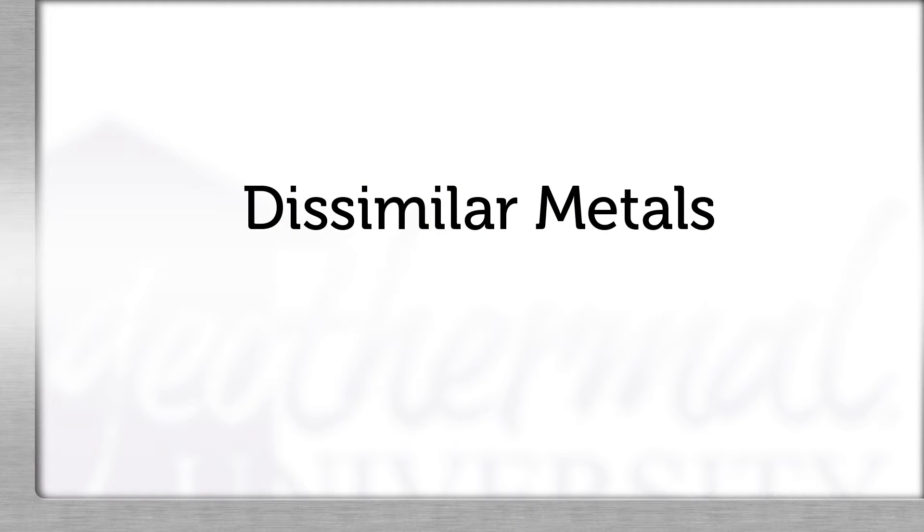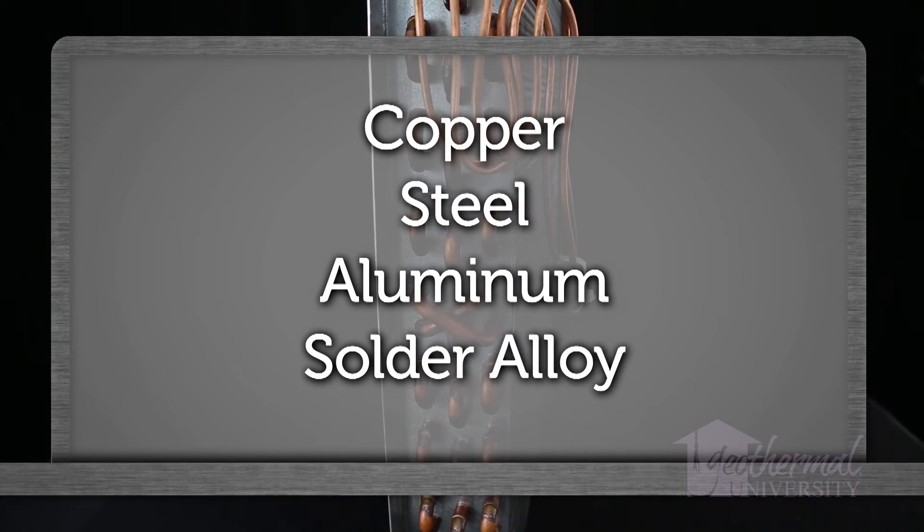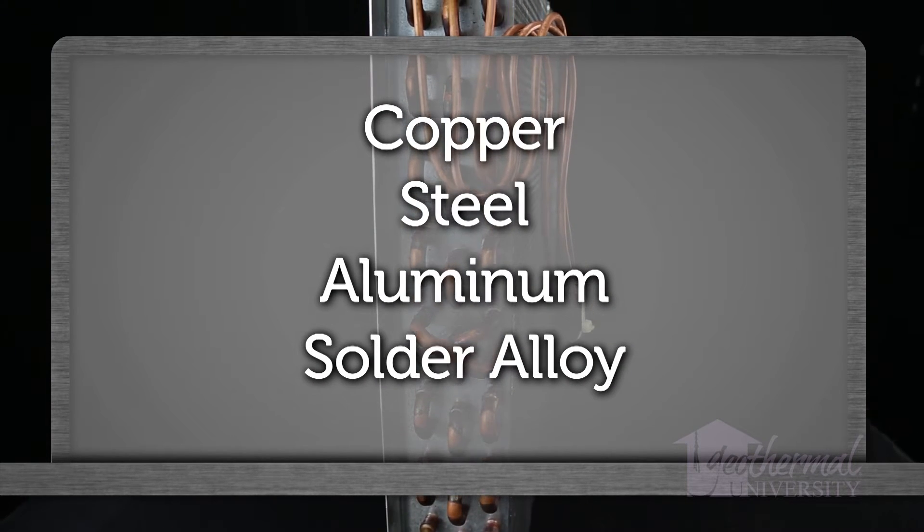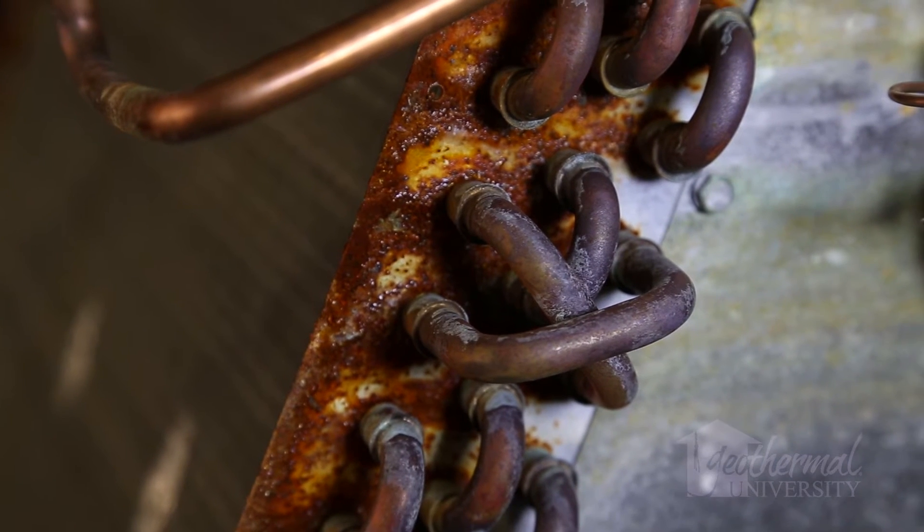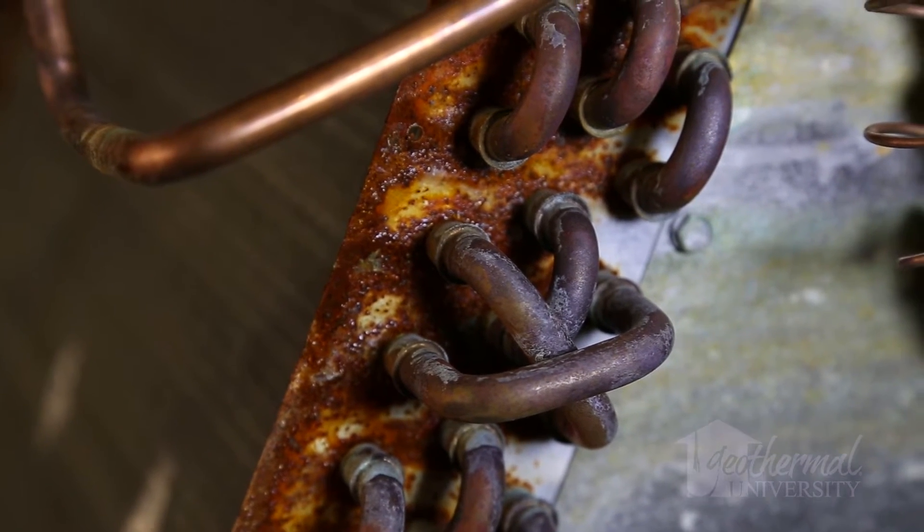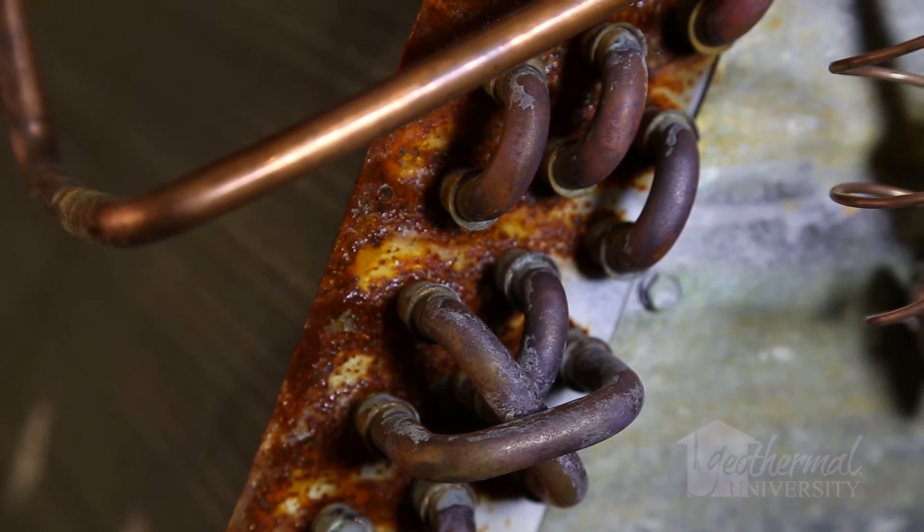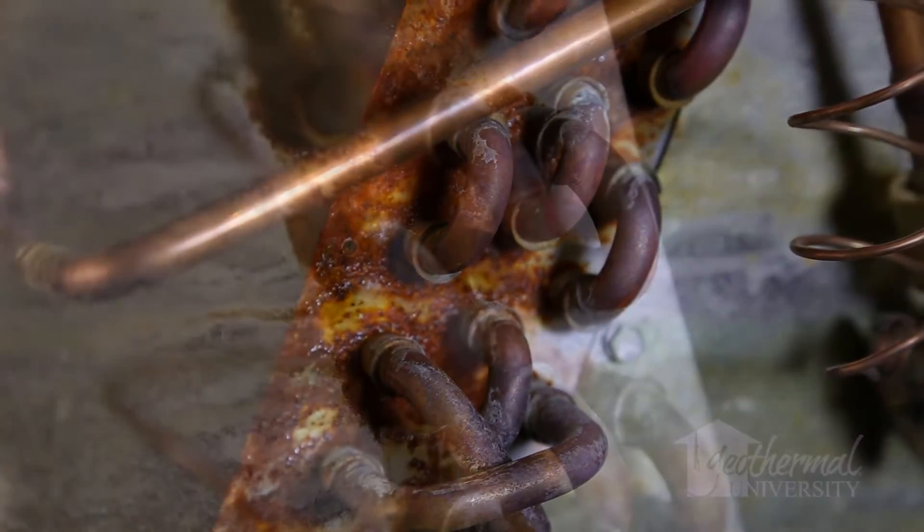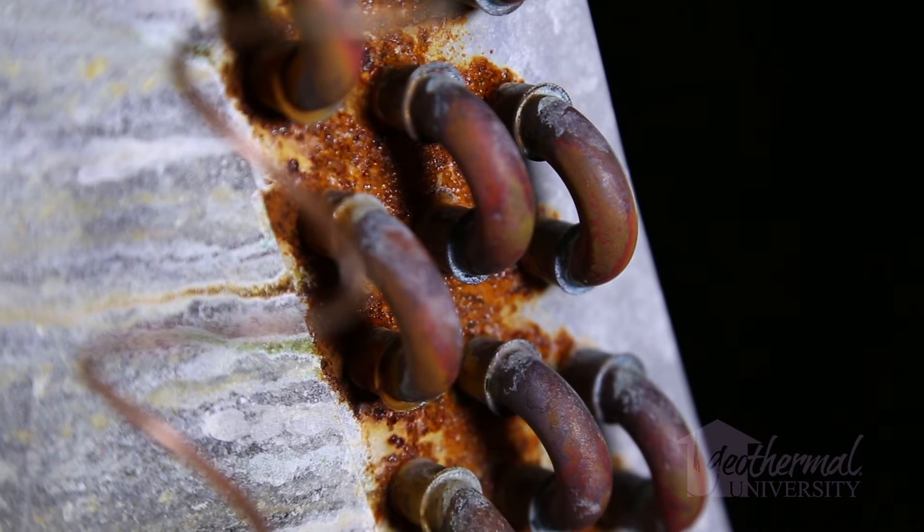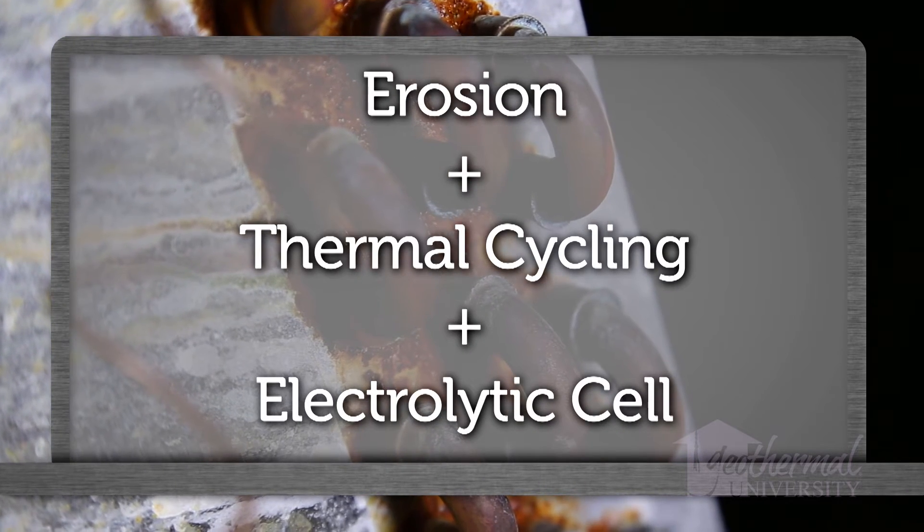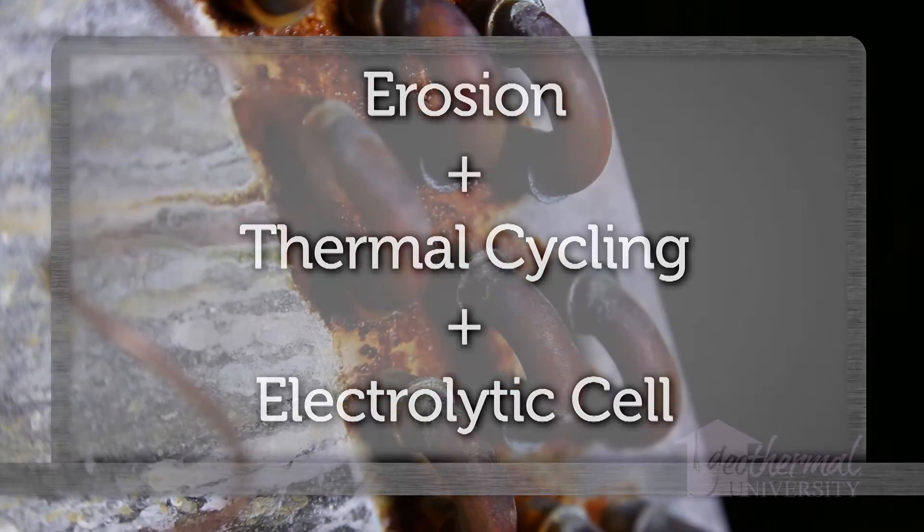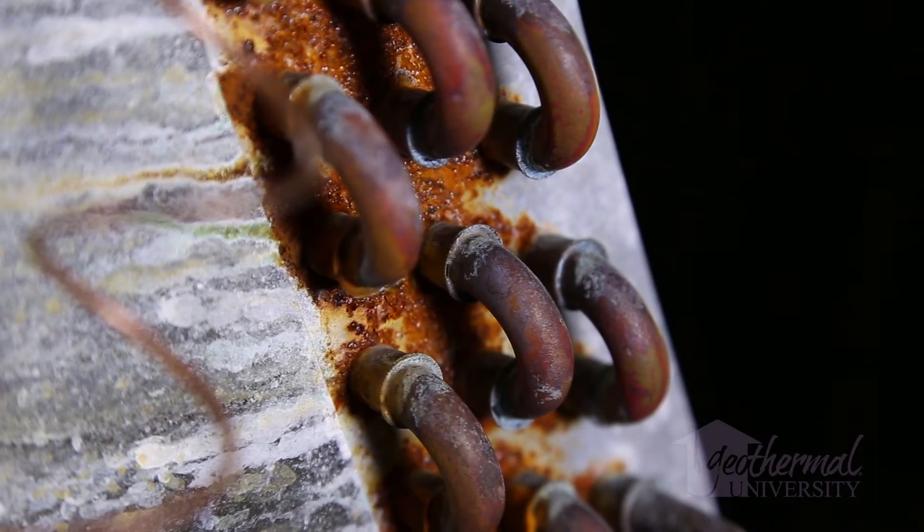Dissimilar metals are used in the construction of many coils. Materials include copper, steel, aluminum, and solder alloy. The result is a slightly corrosive cell. In many cases, coils are installed in harsh environments where high levels of volatile organic compounds speed up the corrosion rate. In summary, you have erosion and thermal cycling along with an electrolytic cell. This combination ultimately leads to coil failure.